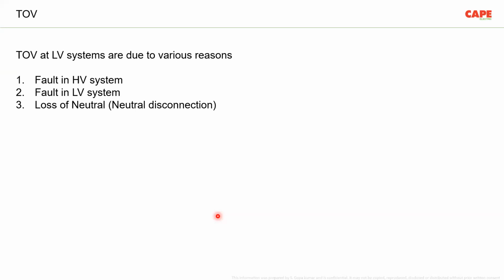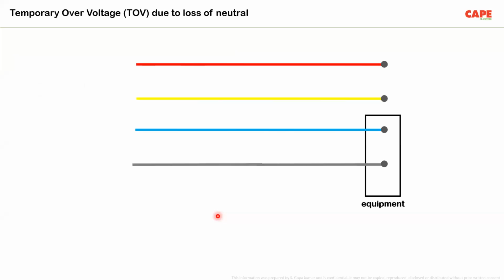In this case, where this particular explosion happened, the neutral from the petrol station to the transformer was disconnected the previous day, and some of the circuit breakers tripped. Without realizing the neutral disconnection, they tried to switch on the panel board, and it exploded. Now, how does it work? I'm just trying to explain it through a single line diagram. You can see a three-phase and a neutral connection.